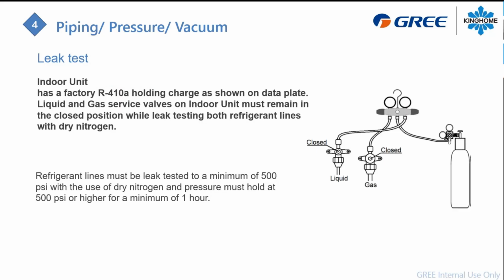So, leak test. As I said, you will find a service valve at the outdoor unit, and you will find a service valve at the indoor unit, even if it's a case coil from King Home or an air handler. Inside the case coil or the air handler, there's already a small amount of refrigerant, like 9 ounces, something like that. So half a pound of refrigerant is already in that indoor coil.